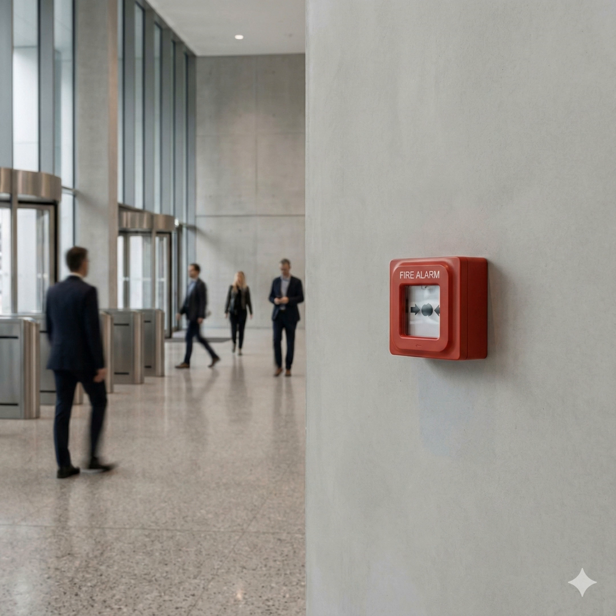Let's talk interoperability again. How important are open standards like BACnet or Modbus for the facility managers who interact with the system every day? They are crucial for unified building management. Open protocols let the fire panel integrate with a larger building automation platform. This lets facility managers use a single interface to view alarm history, system status, and troubleshoot faults across everything: HVAC, lighting, security, and fire systems.